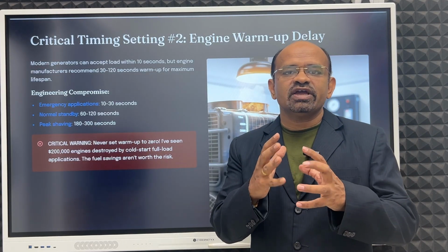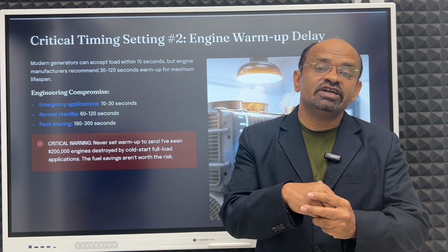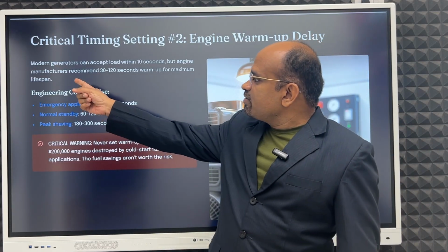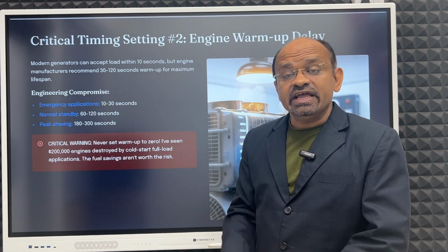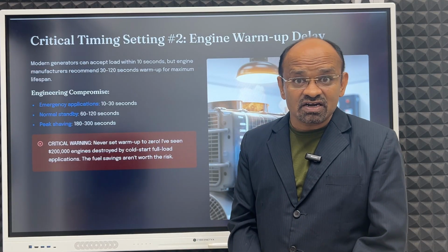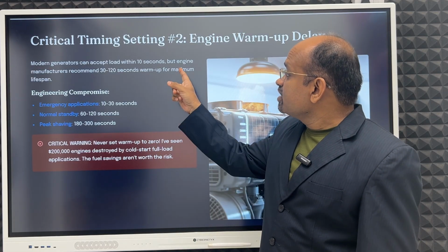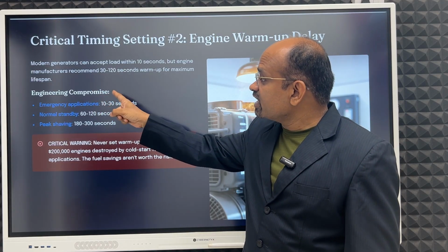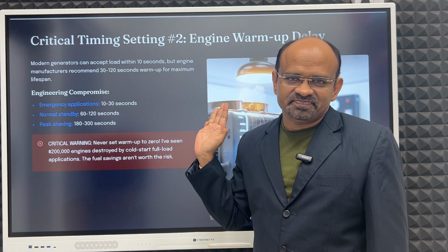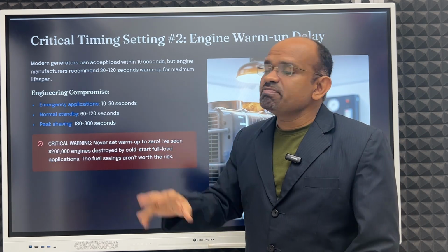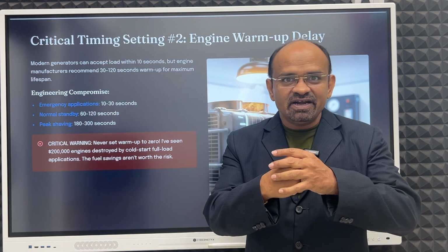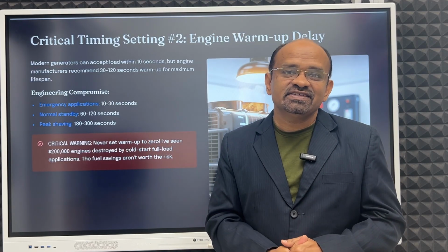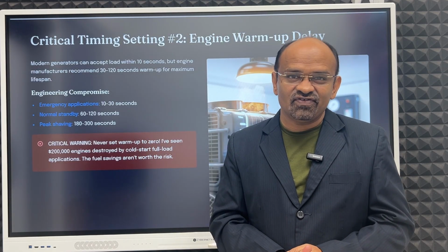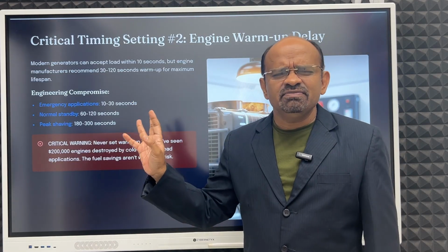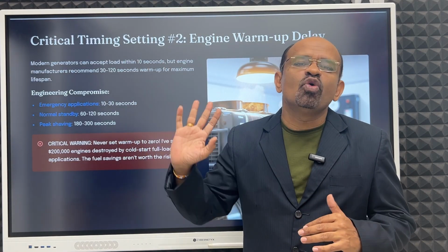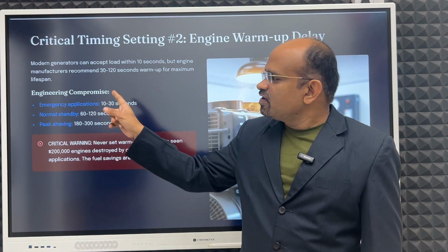Engine should warm up. It should reach proper speed, and then we should put it on load. Modern generators can accept load within 10 seconds. Modern generators are smart; within 10 seconds, they can take the load. But engine manufacturers recommend a 30 to 120 seconds warm up for maximum lifespan. Abrupt or very fast load taking can deteriorate its life. If you take 30 to 120 seconds, its lifespan will be longer. So they will advise you this.